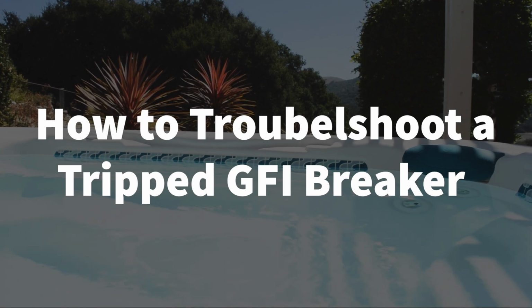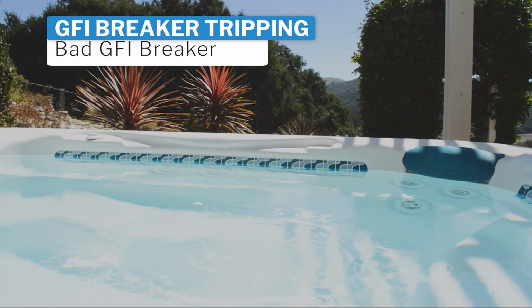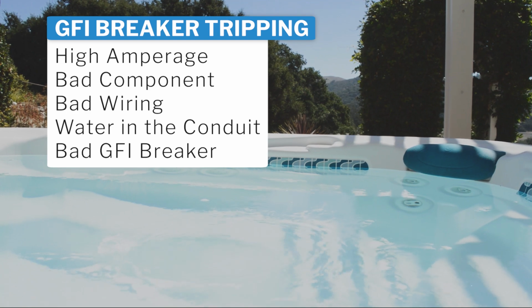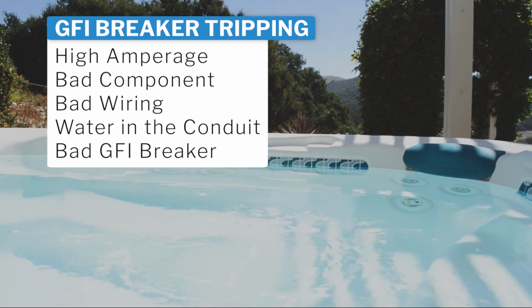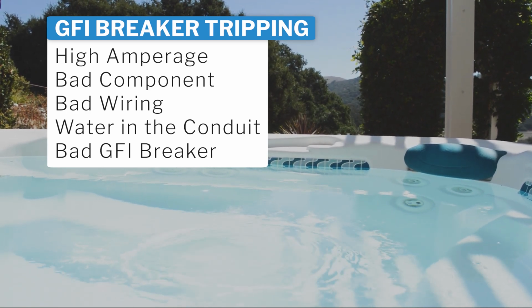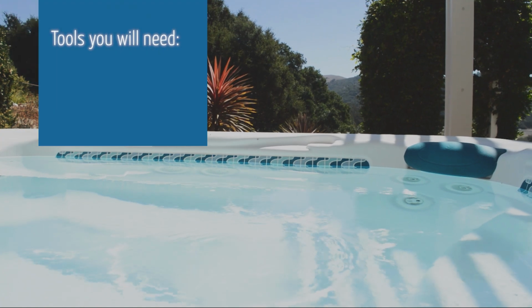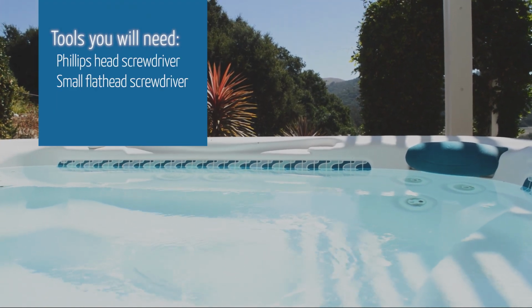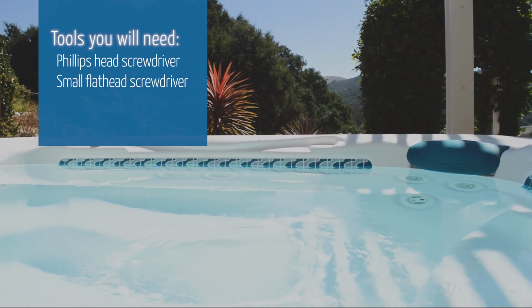When the GFI breaker trips, it is because of high amperage draw, a bad component, bad wiring, water in the conduit, or a bad GFI breaker. Before we get started, let's go over the tools you will need. Tools you will need: Phillips head screwdriver, small flathead screwdriver.